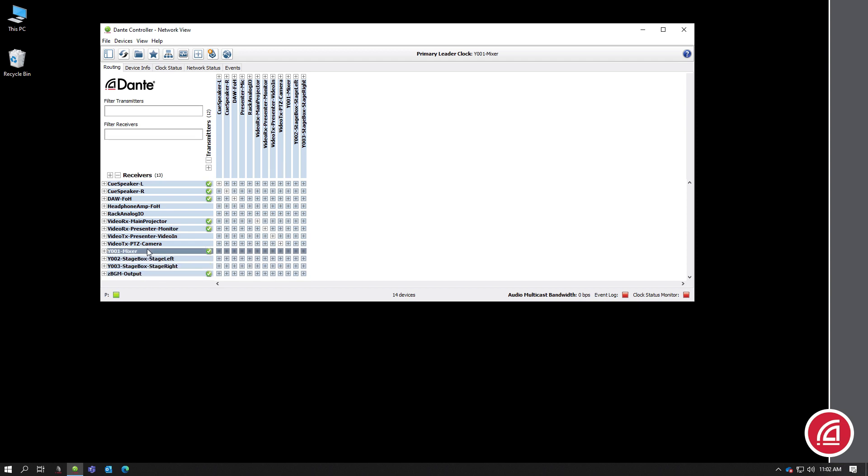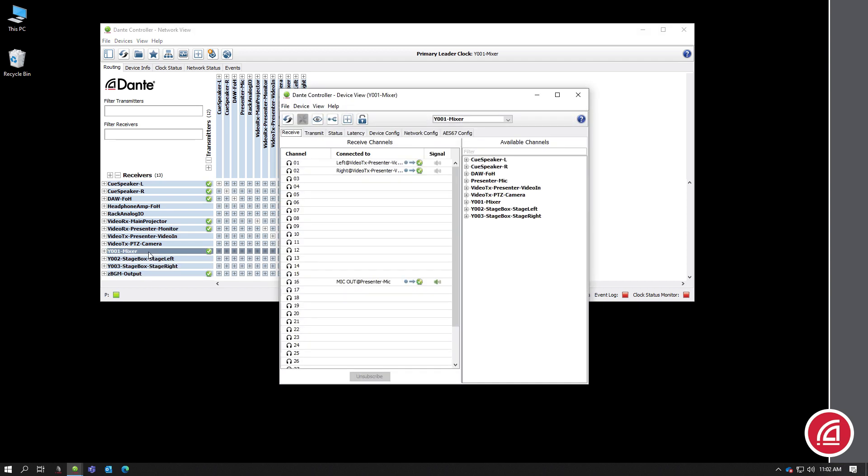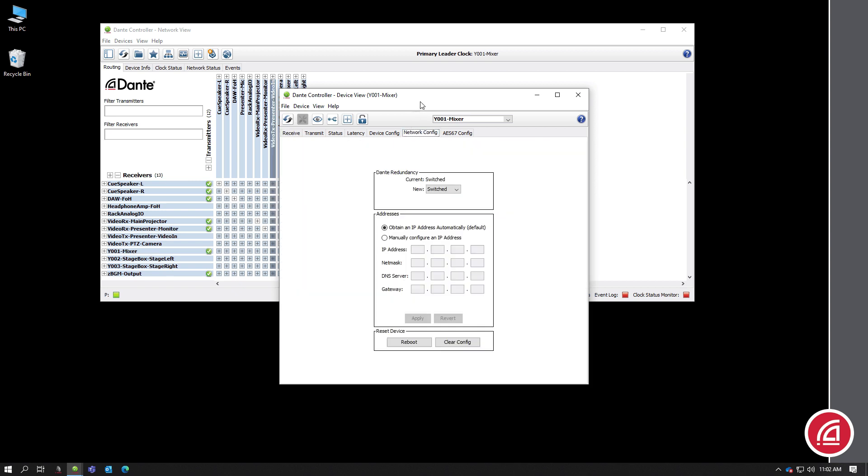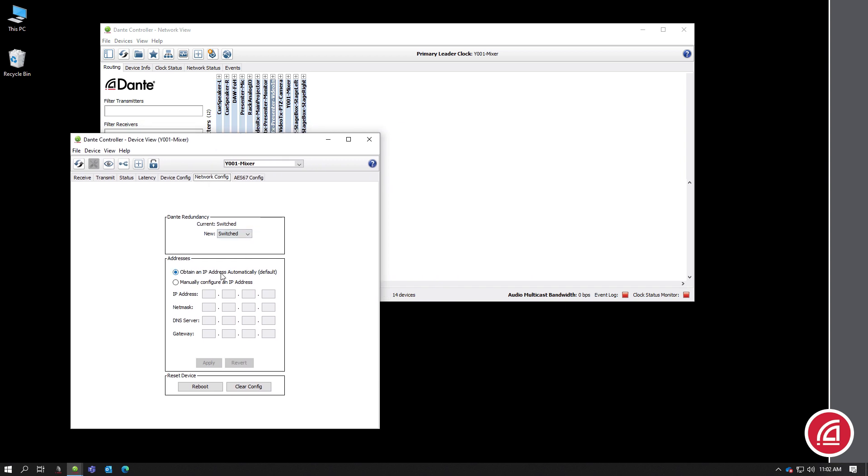If you're in network view, just double click on the device you want to edit, and that will give you a device view window. In that, choose the network config tab. Here you'll find options for automatic IP, like DHCP, or static configuration. If you want to set a static IP, just click the radio button and enter your settings. Click apply for the settings to transfer to the device. You'll likely need to reboot the device for the settings to take effect. Some devices can use the soft reboot button here in this menu. Others may require physically cycling the power.